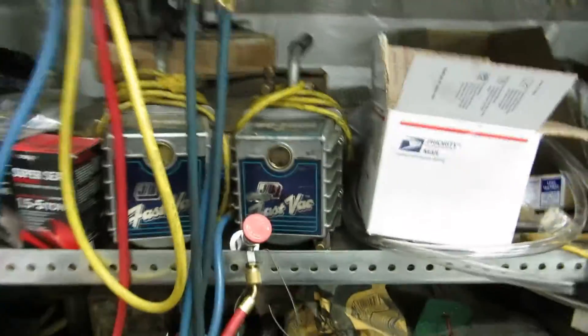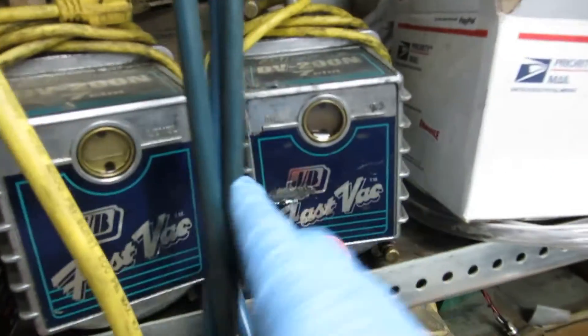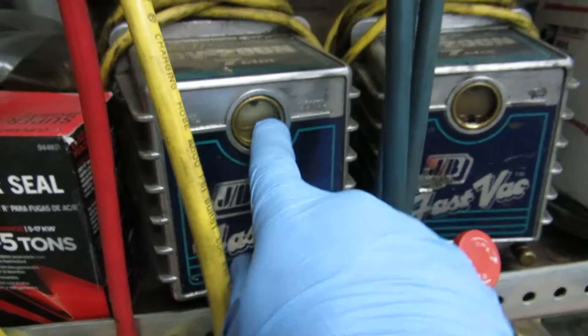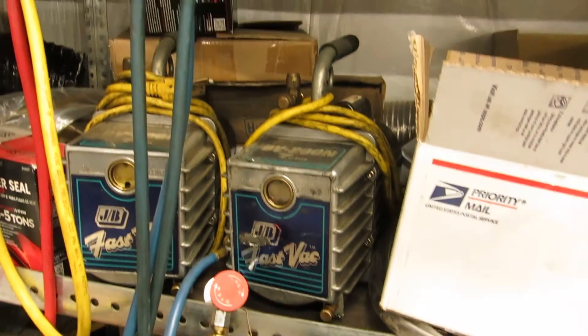Look at that - good, 500 is what we shoot for. That's great. There's my old pumps I used to use - JB-7s. The problem with these is they leak around the gasket here for some reason, and the legs - the rubber legs if you're getting oil on them they're just deteriorating. But these are still probably good pumps, I just upgraded. I had these a long time, they treated me well for years.